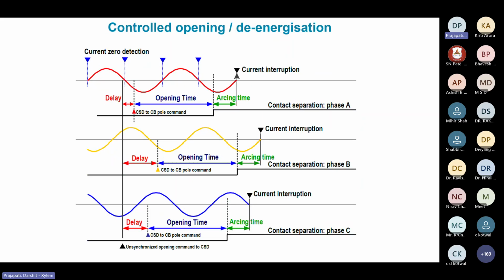Let's see the control opening or the de-energization. So here again, the opening time might be the same or different for all three phases, and the delay will be added. And also here, the arcing time, which we discussed, is a reignition-free window, which can also be considered over here. So the arc is not going to restrike or reignite.